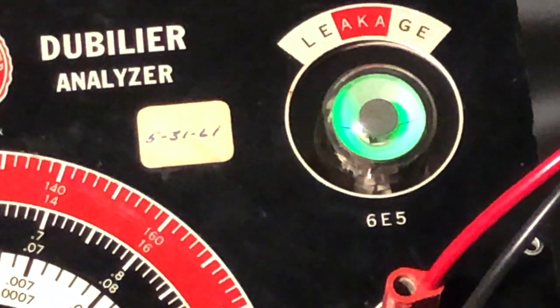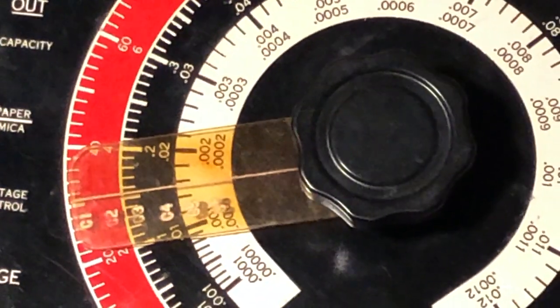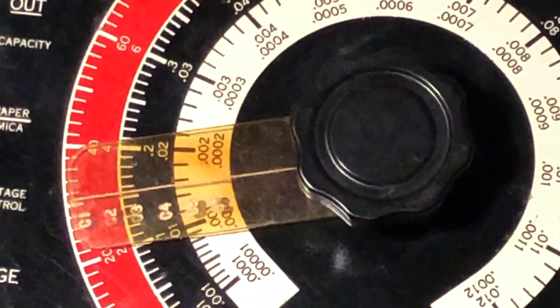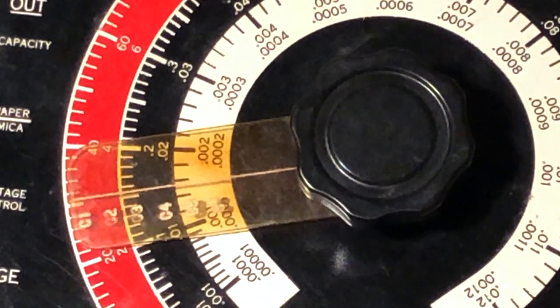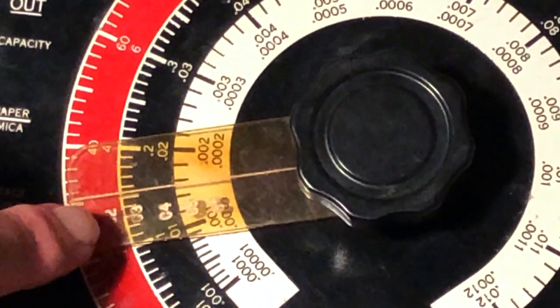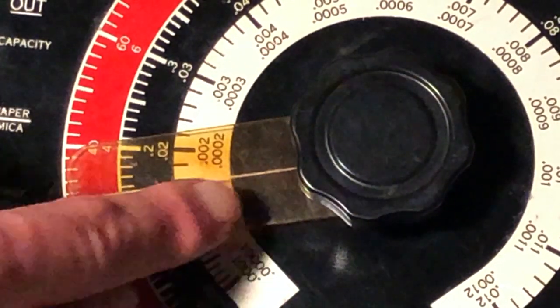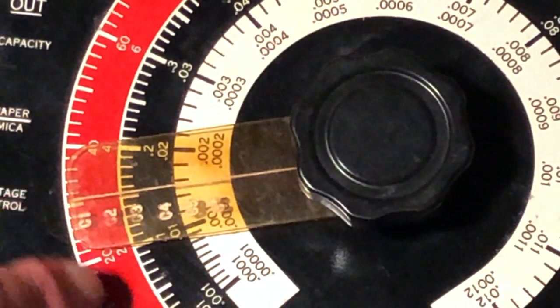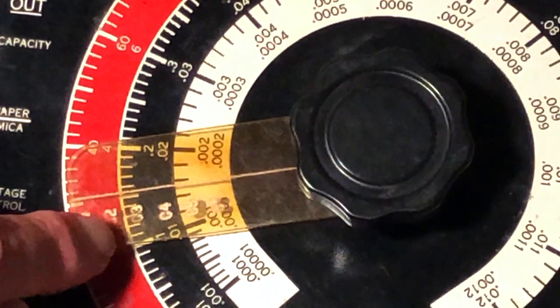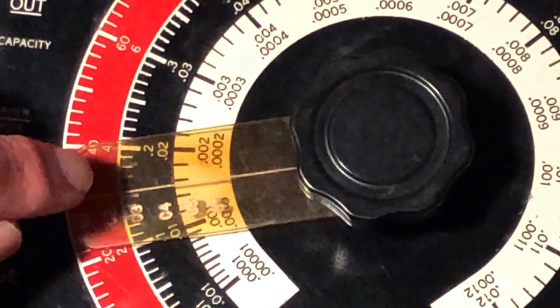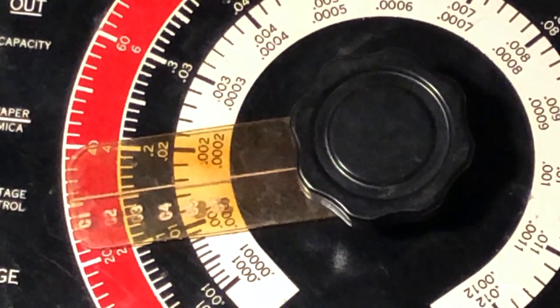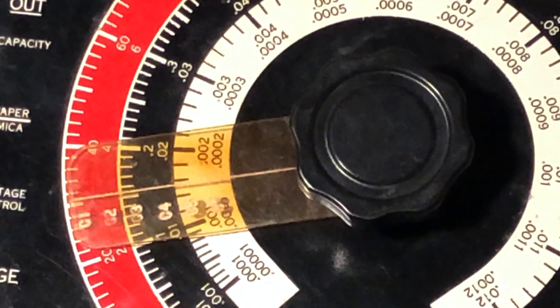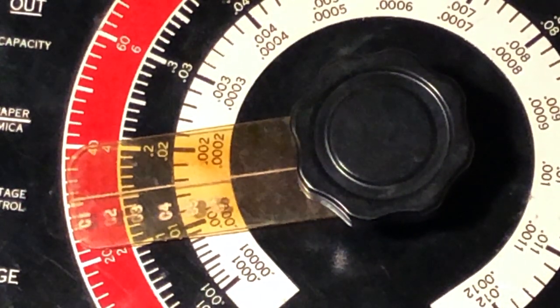Really appears to be the maximum that the eye will open. And again, looking at the setting of the control, just swing the camera over here. You can see we're on the second scale in, because it's on the C2 scale. So C1, C2, 3, 4, 5, and 6 going in. So C2, we have 0.2, then 2, 3, and then 4, and you can see this line is right on the 3 microfarad. So very, very accurate. The tester is certainly functioning correctly at this point, and in both the leakage and the capacity tests.